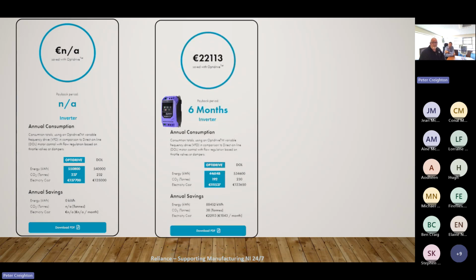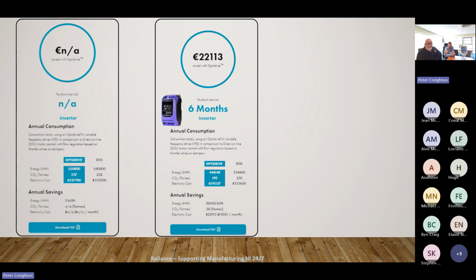So we looked at the original cost of running that motor, which was 137,700 euros, and it was emitting 237 tons of CO2. So what we did is we looked at putting on the inverter first, and the inverter gave a saving straight away of 38 tons, and an electricity saving of 1,843 euros. And we were now down to a running cost of 111,537 euros, with a 6-month payback just for putting on an inverter.